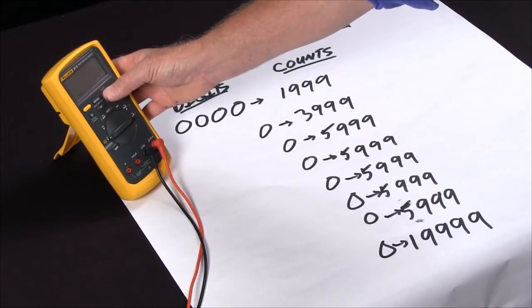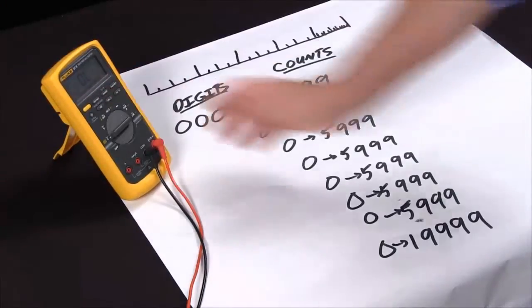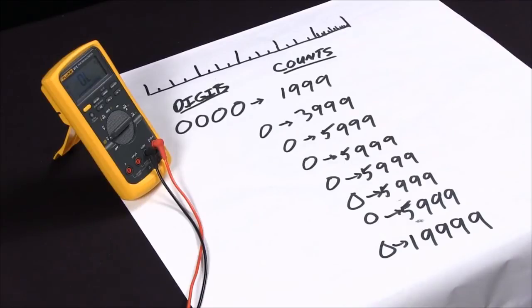If I force it into its lowest range, in this case, which is the 600 millivolt range, we see OL on the display. Never take OL to mean that that's an open line. That means overload. There's more voltage on there than the range can measure.